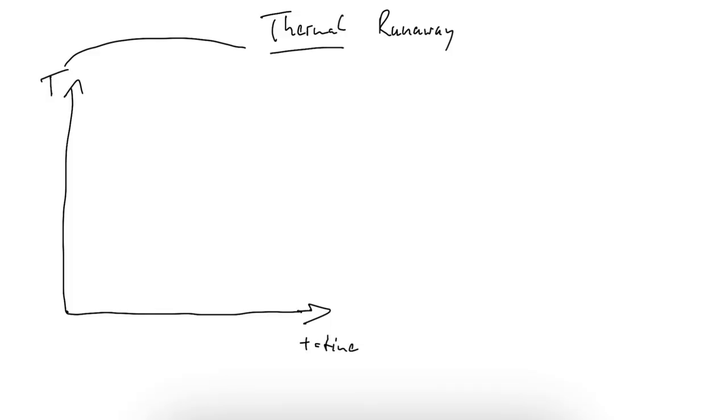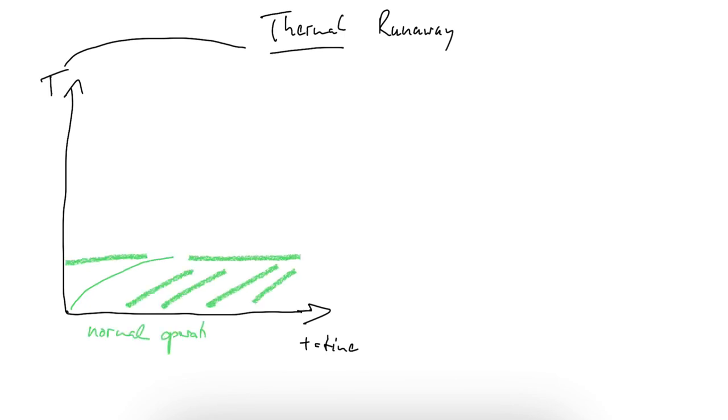In the very beginning, you have a very slow heat increase. Something starts and the cell slowly heats up, getting warmer and warmer. At this point you can still interrupt it — you can stop it by applying cooling or by stopping the energy intake, the reason why the cell heats up. Very often it has to do with electricity, and really switching off and cooling is the best way — you can pretty much contain it.